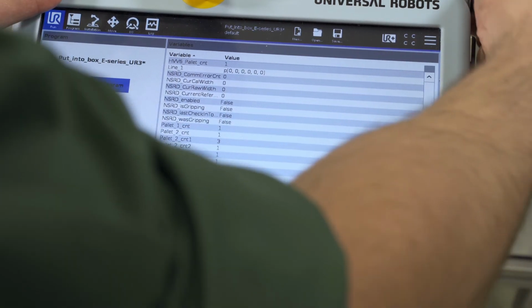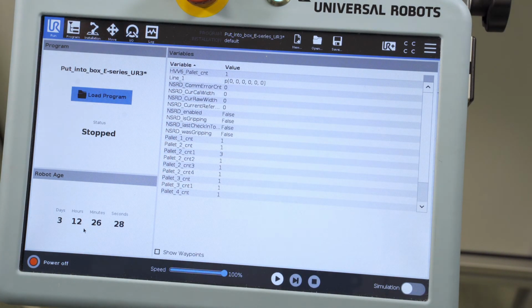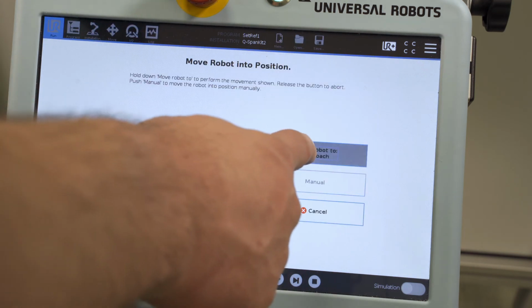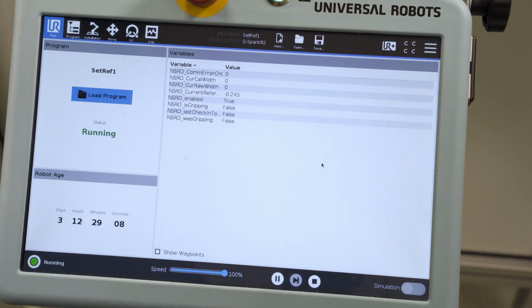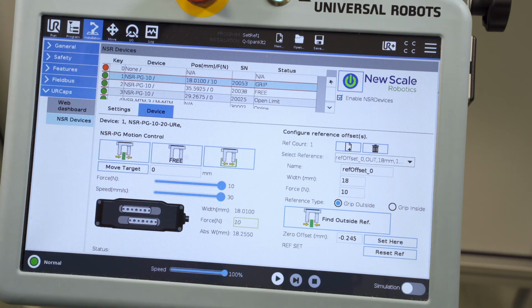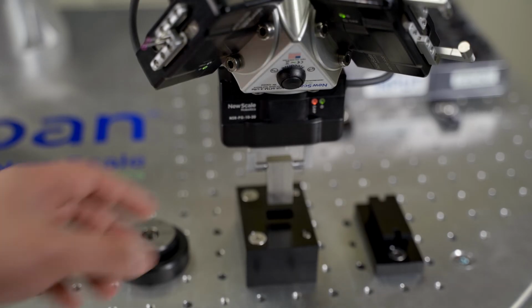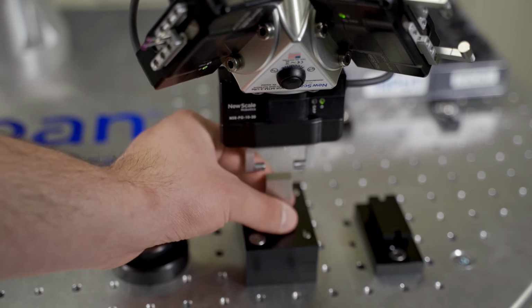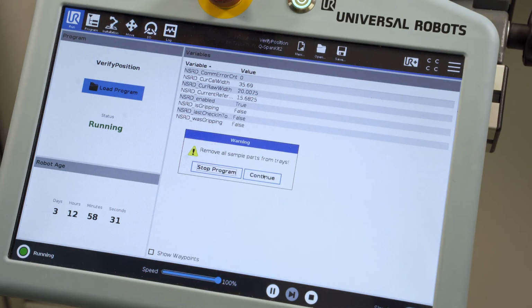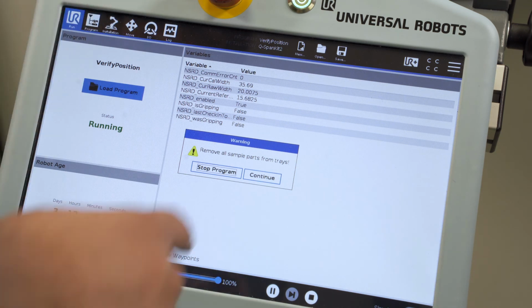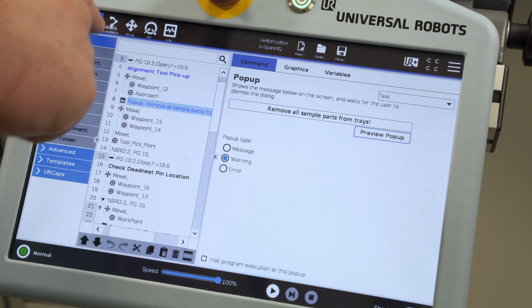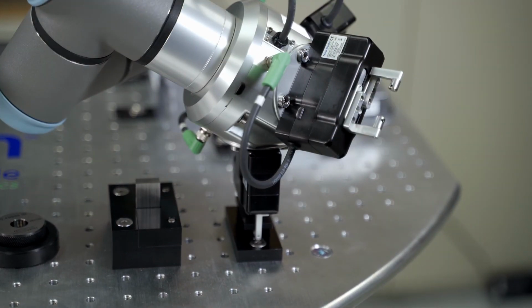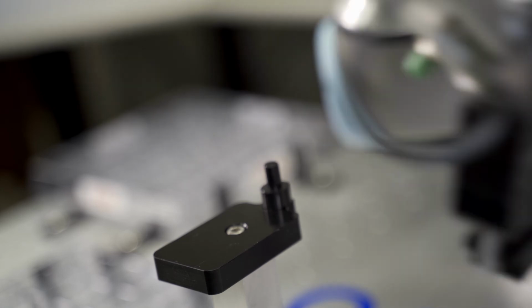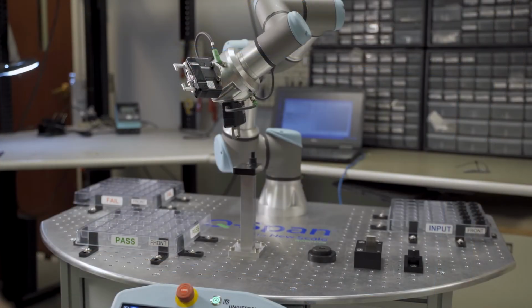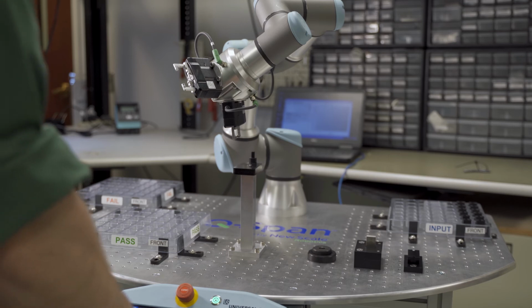Before running the kit's demo program, calibration of the grippers is required, as well as position verification of all the system's components. This is done using a number of programs included on the Q-Span kit's USB stick. The Q-Span installation guide can run you through the step-by-step procedure of calibrating each NewScale gripper. After calibration is complete, there is a verification process used to determine that the robot as well as all the kit's accessories are aligned correctly so that the program can run smoothly. Detailed instructions for this are also included in the Q-Span manual. After calibration and position verification, the demo program is ready to run.